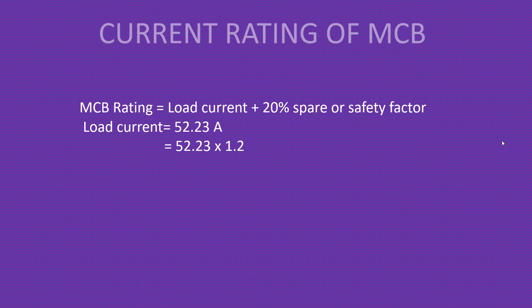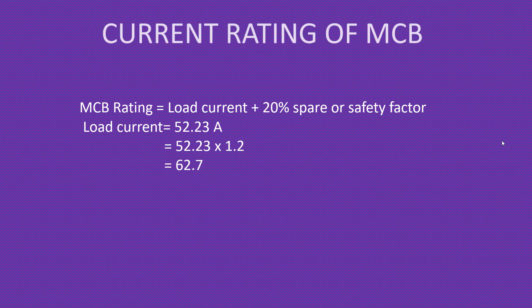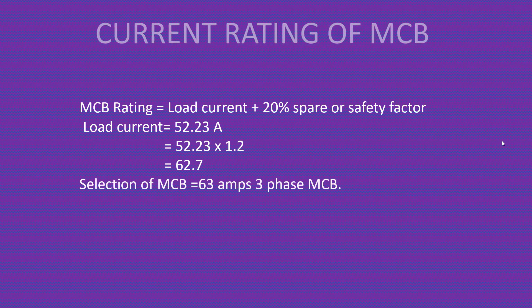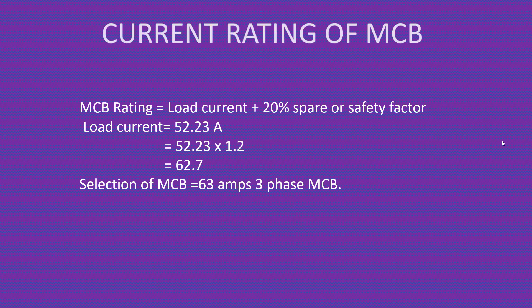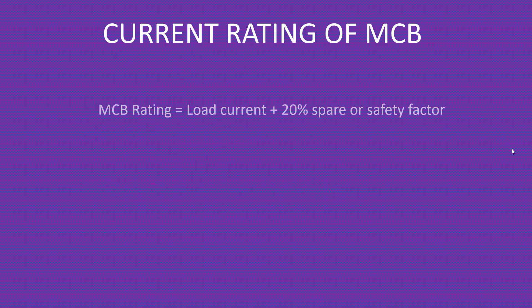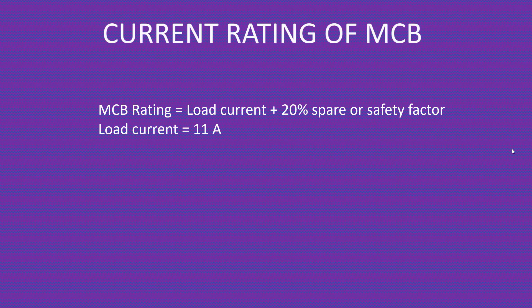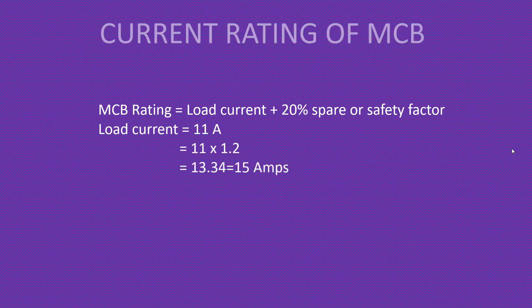For our three-phase load current of 52.23 amps, the MCB rating will be 52.23 × 1.2 = 62.7 amps. Looking at the MCB chart, we select the next available rating, which is 63 amps — because no manufacturer makes a 62.7-amp MCB. So our selection is a 63-amp three-phase MCB. For the single-phase scenario, the load current is approximately 11 amps, so 11 × 1.2 = 13.34. The next available rating is 15 amps, making our selection a 15-amp single-phase MCB.